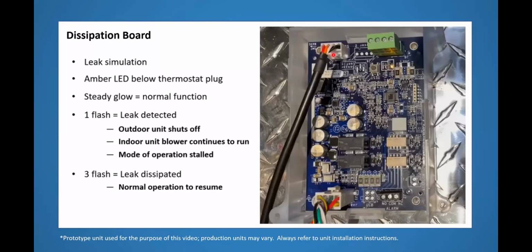If it's a residential furnace split system, you have to install this stuff because they don't know whose furnace you're going to have. Are you going to reuse an old furnace? You getting a new furnace, right? Is it this brand? Is it that brand? They have no idea. So in that case, you're going to get the factory installed leak sensor with a harness dangling out of the evaporator coil, and you're going to plug that into a board, and you're going to wire the board to the condensing unit and the furnace. Not you, but whoever's installing it.